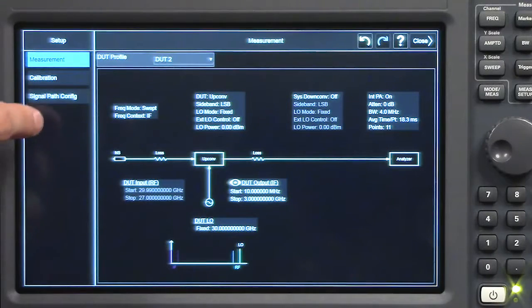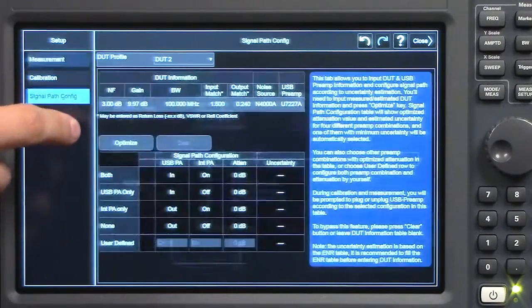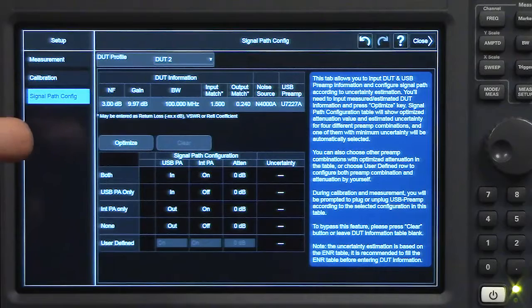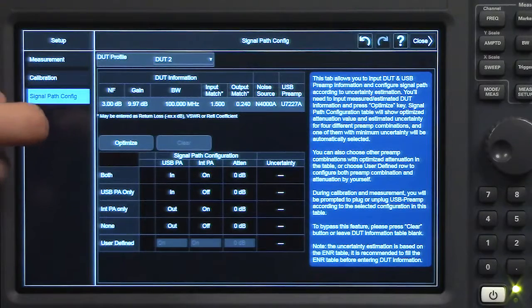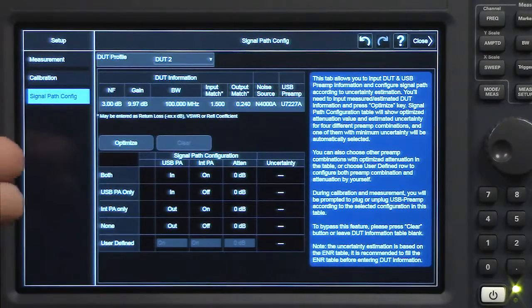Next, let's go to the signal path configuration tab, also known as our noise figure wizard. This tool gives you a ballpark estimate of the uncertainty for your given DUT parameters.